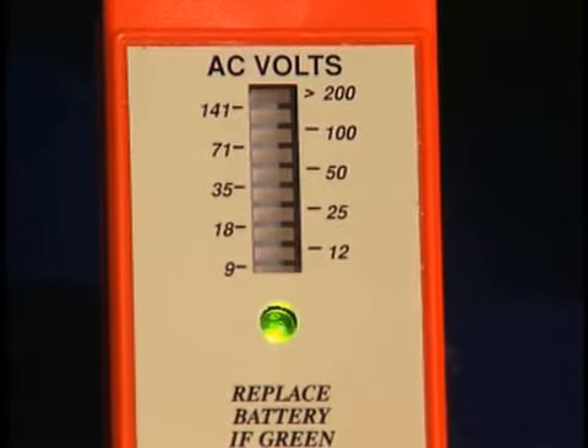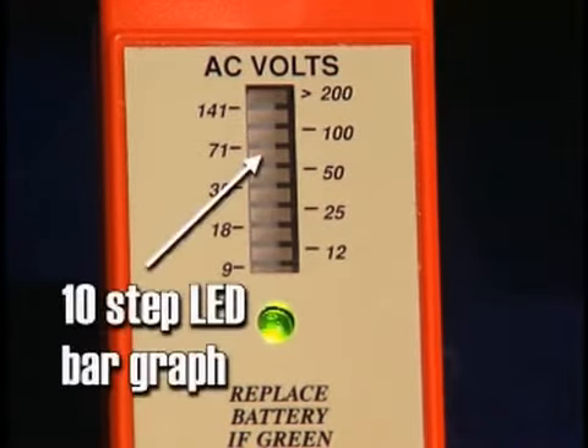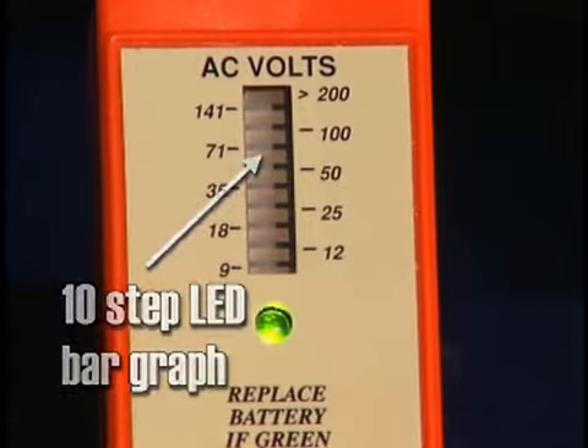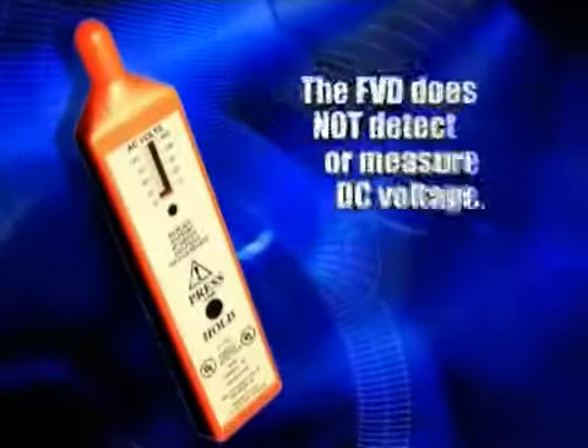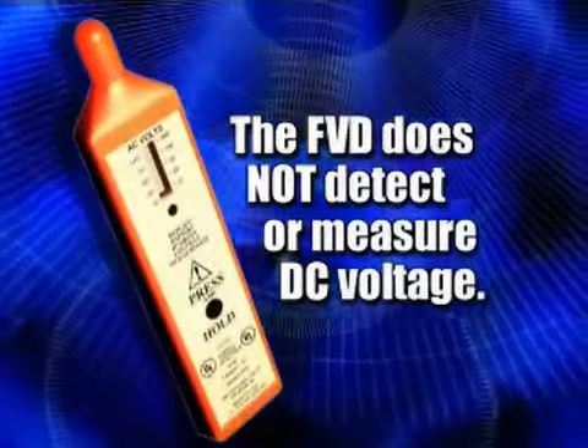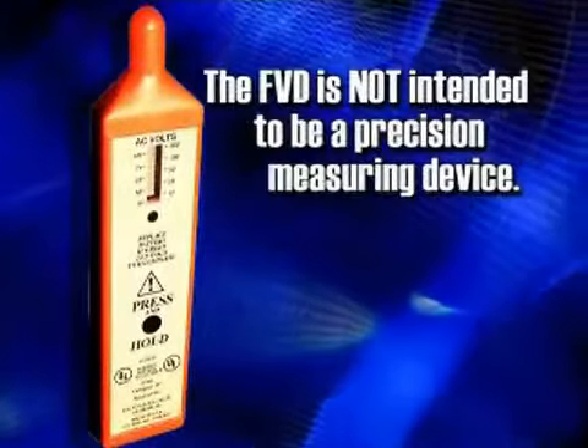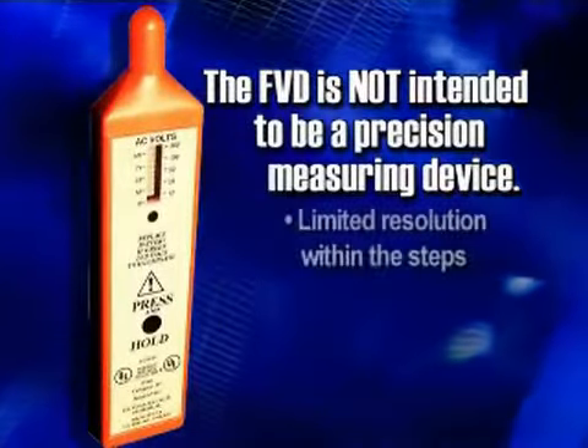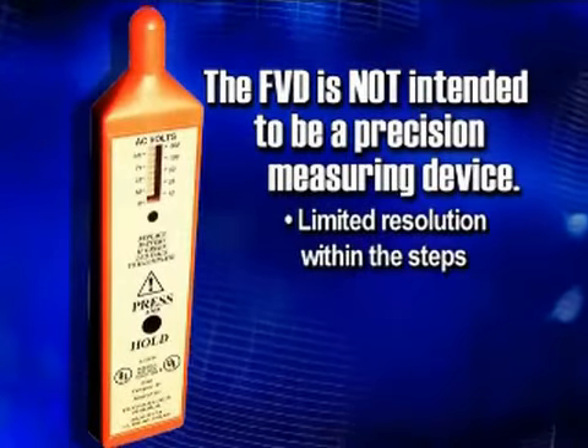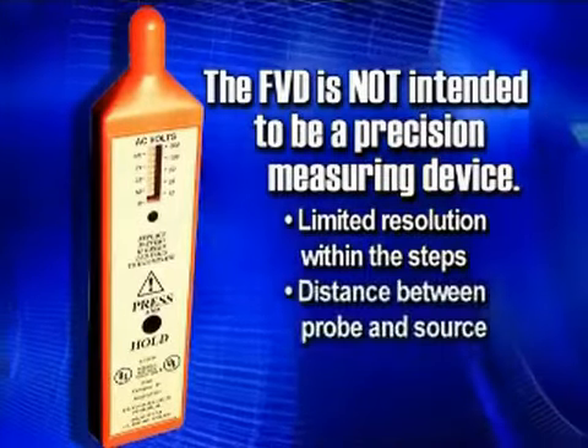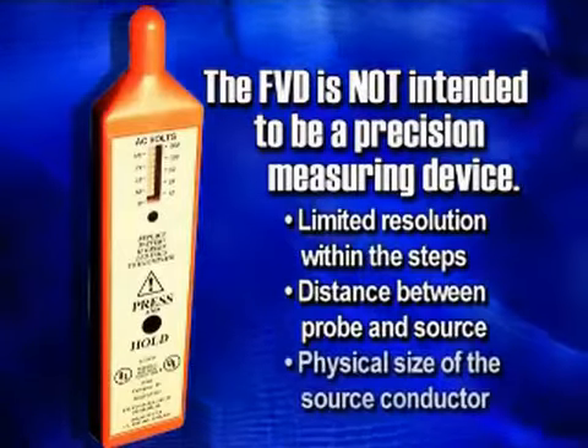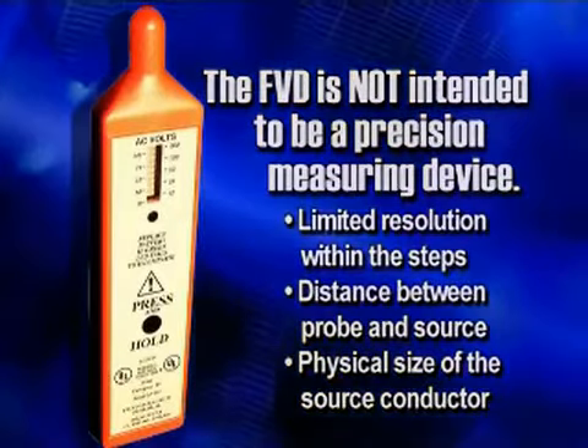Near the probe end is a 10-step bar graph that indicates the amount of AC voltage being detected. The FVD does not detect or measure DC voltage. Please keep in mind that this is not intended to be a precision measuring device. Its precision is limited by the resolutions within the steps, as well as the distance between the probe and the source, and the physical size of the source conductor.